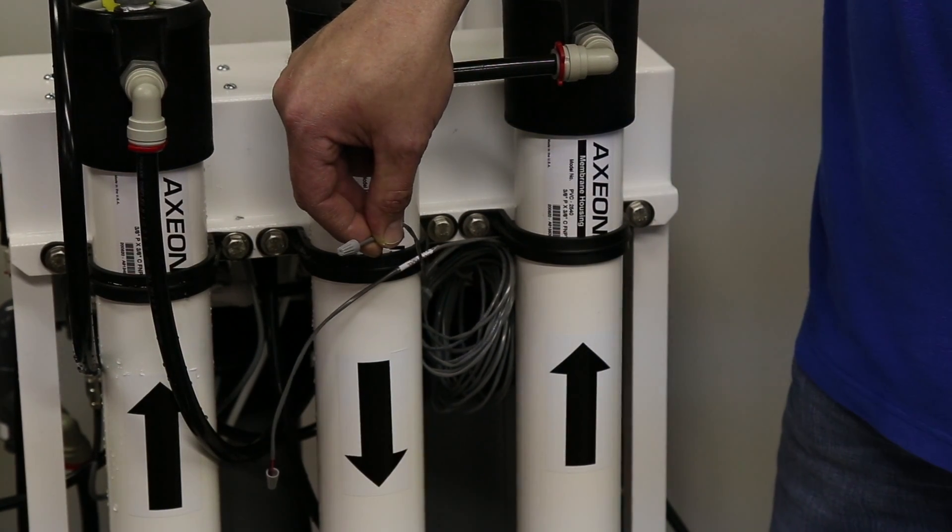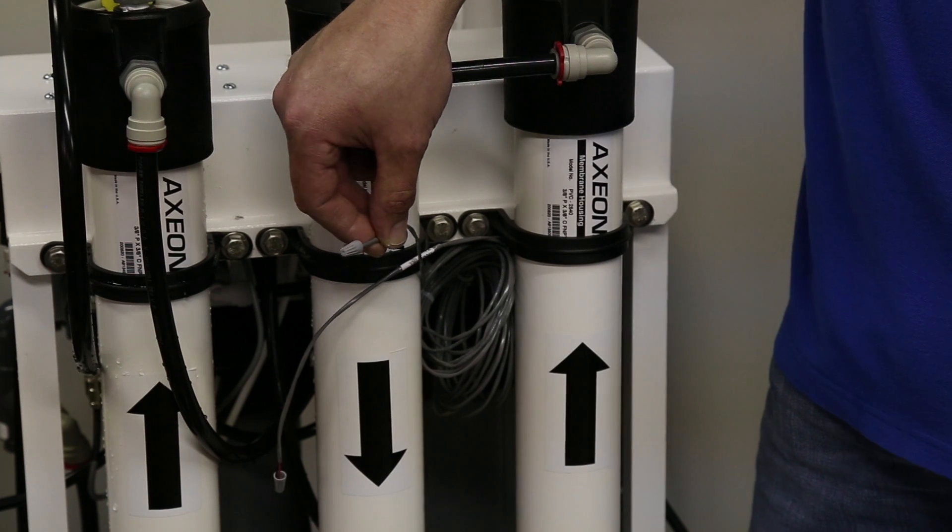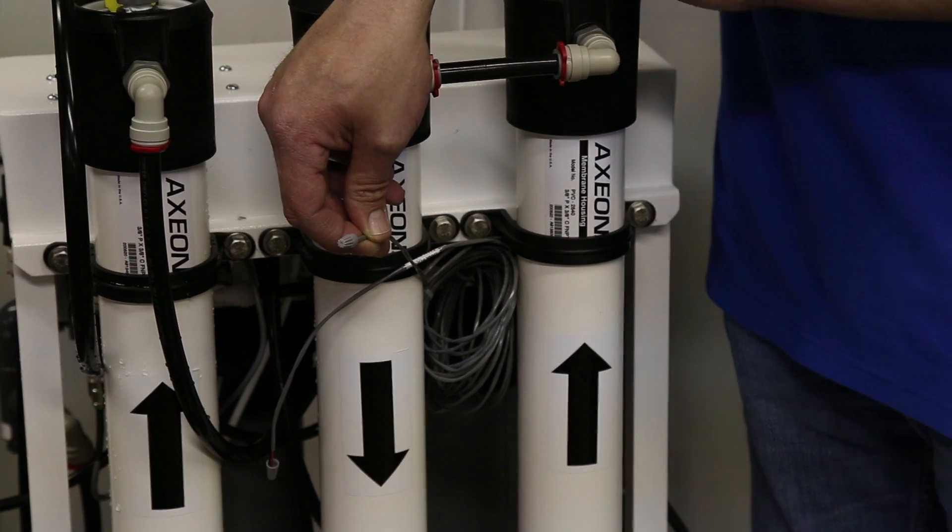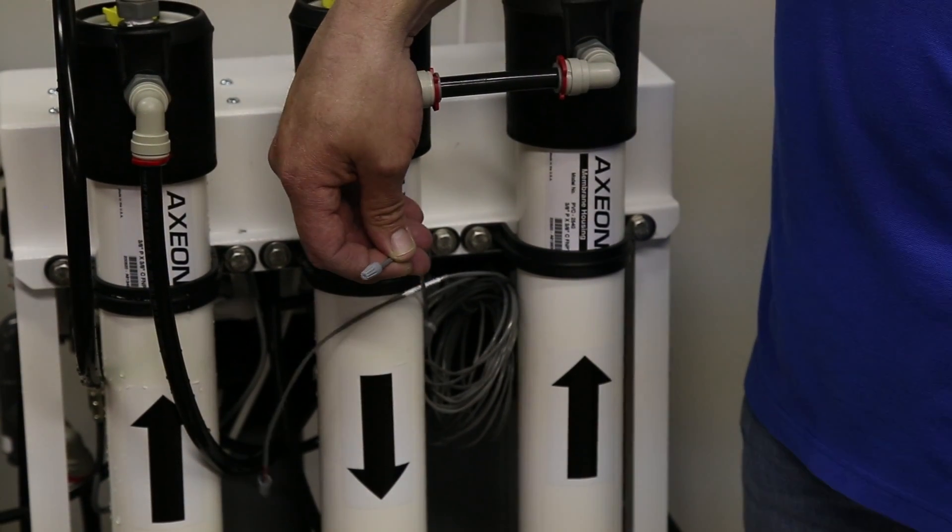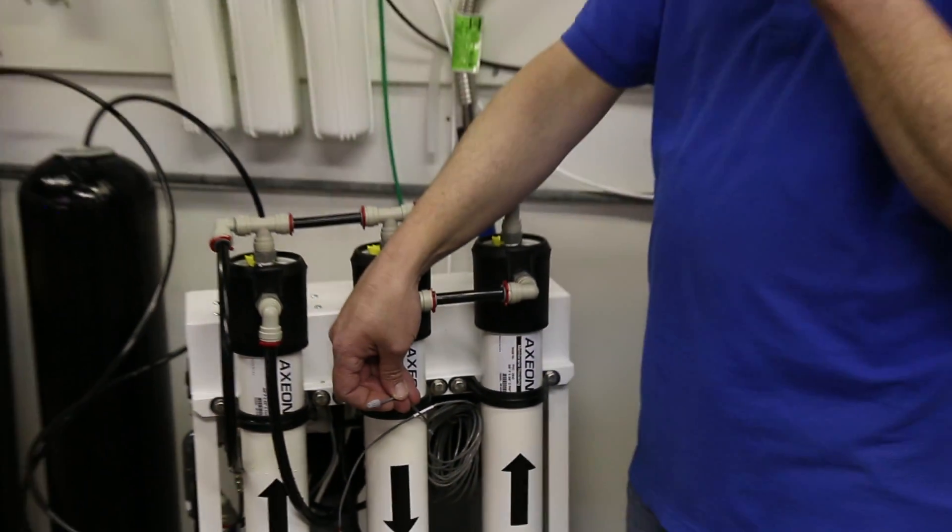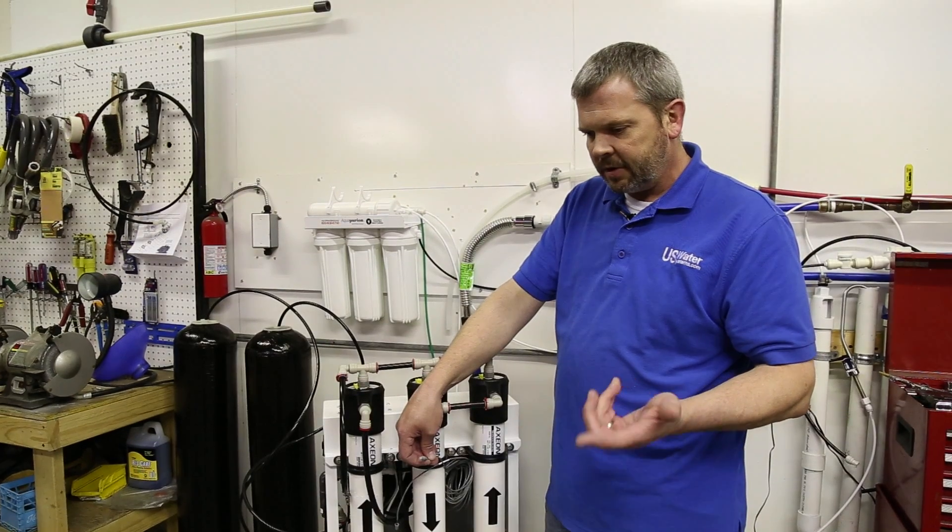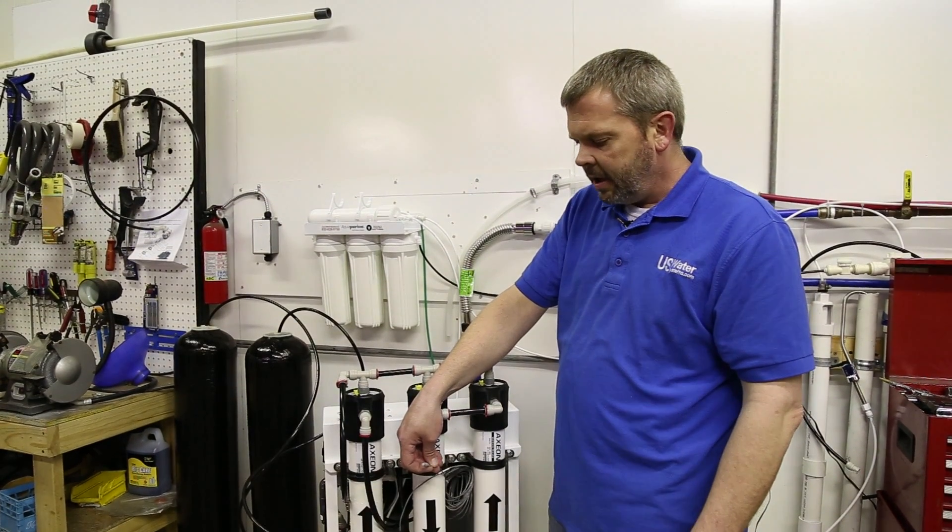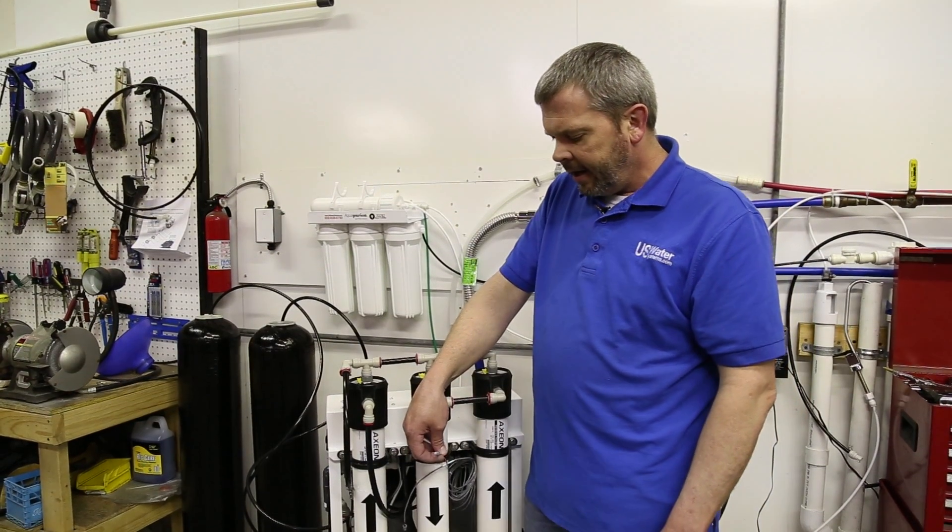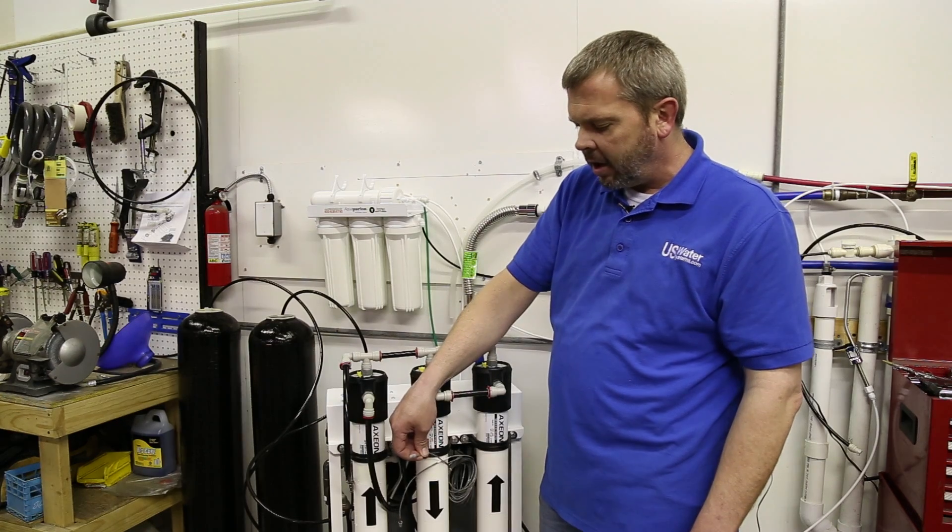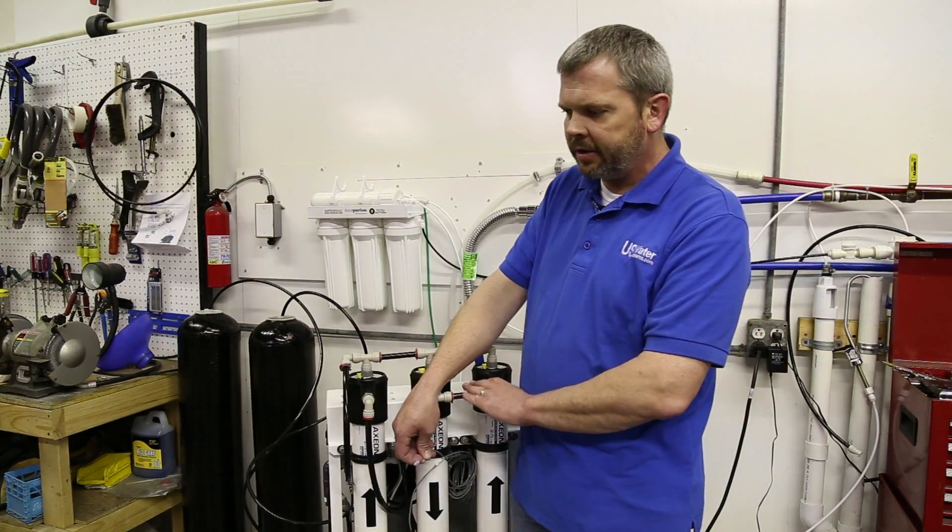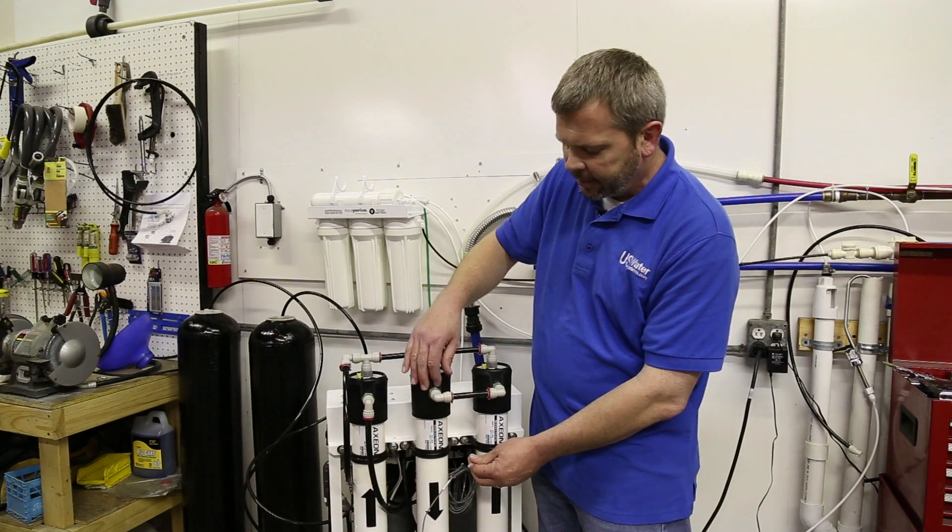That way if your pre-treatment is in backwash or in regeneration, it'll open this circuit and not allow the RO to run while those are actually regenerating or backwashing. Most regenerations or backwashes of filters or softeners are going to allow hard water bypass, so basically untreated water to come by. That's why we want to lock out the RO whenever those are backwashing to ensure we're getting only treated water to the RO system. That's what helps protect the membranes.